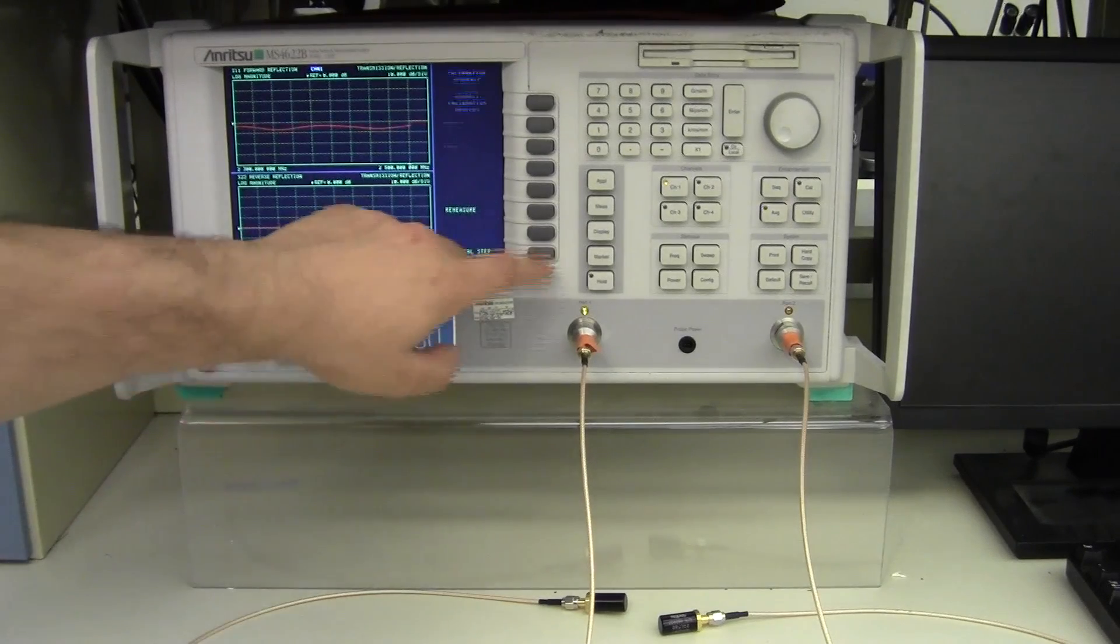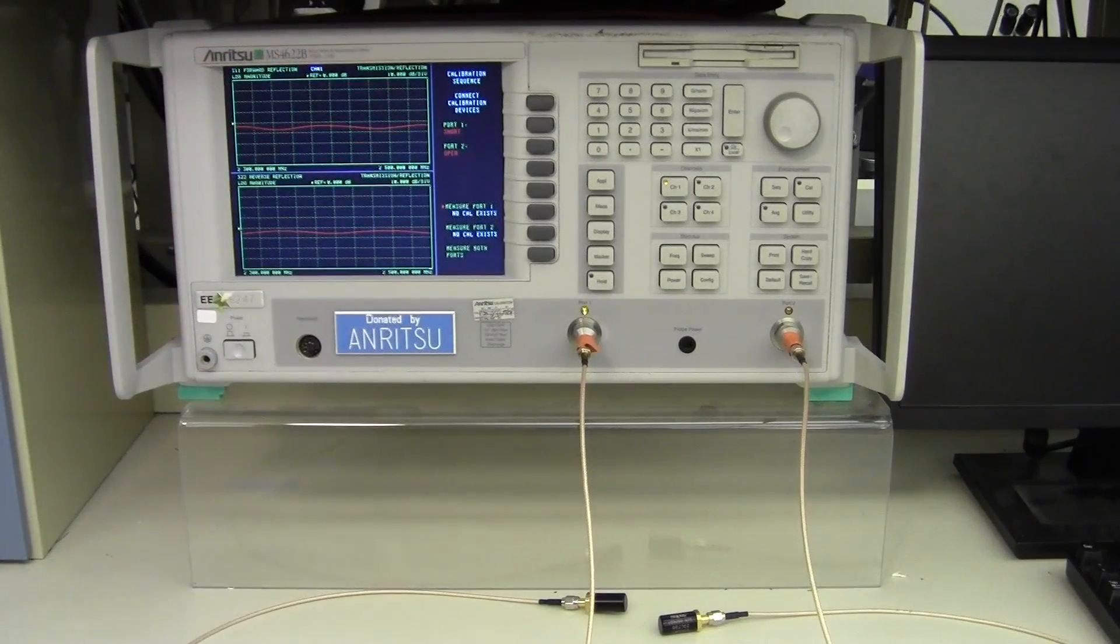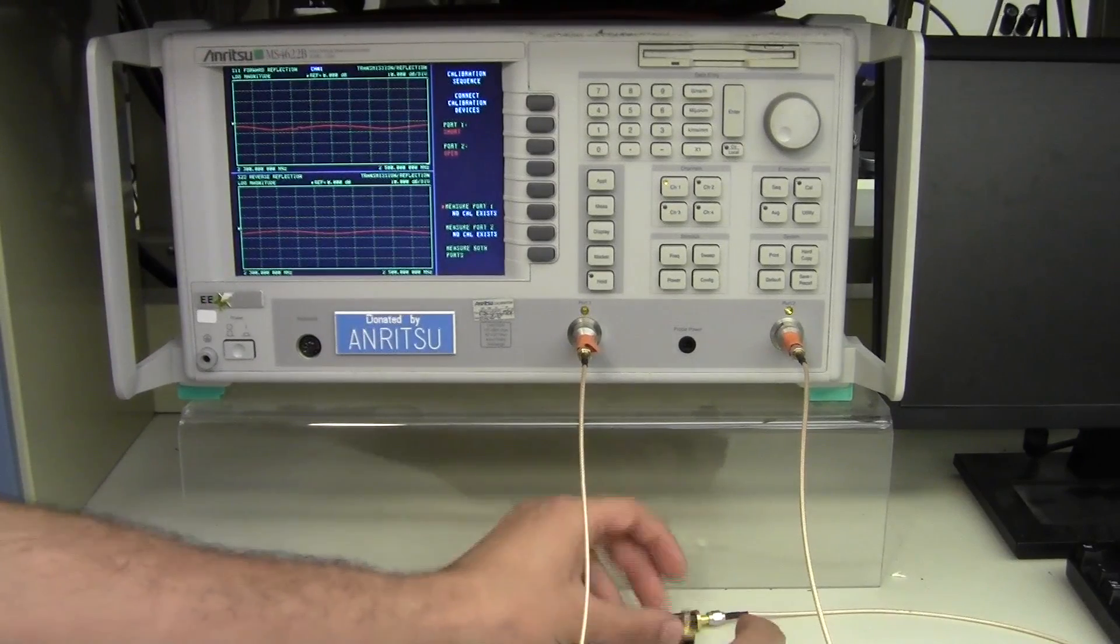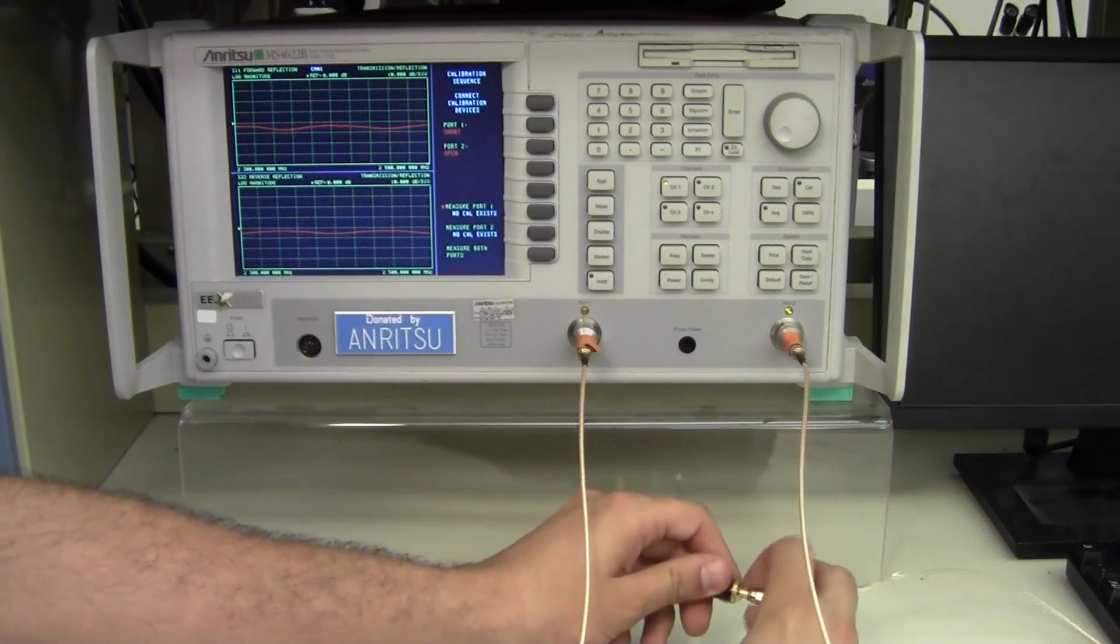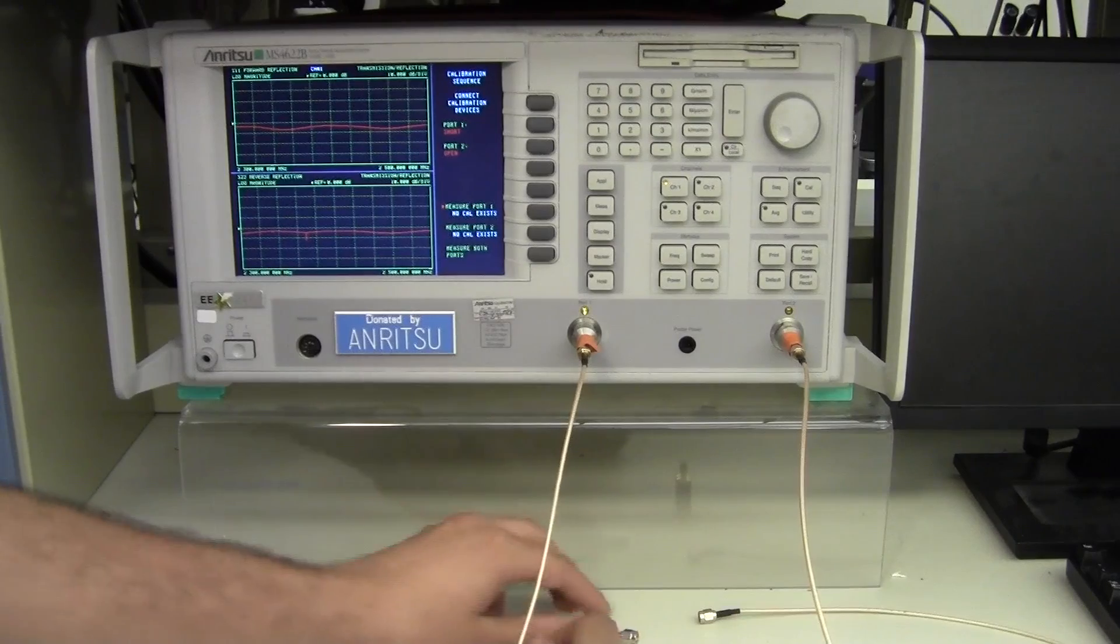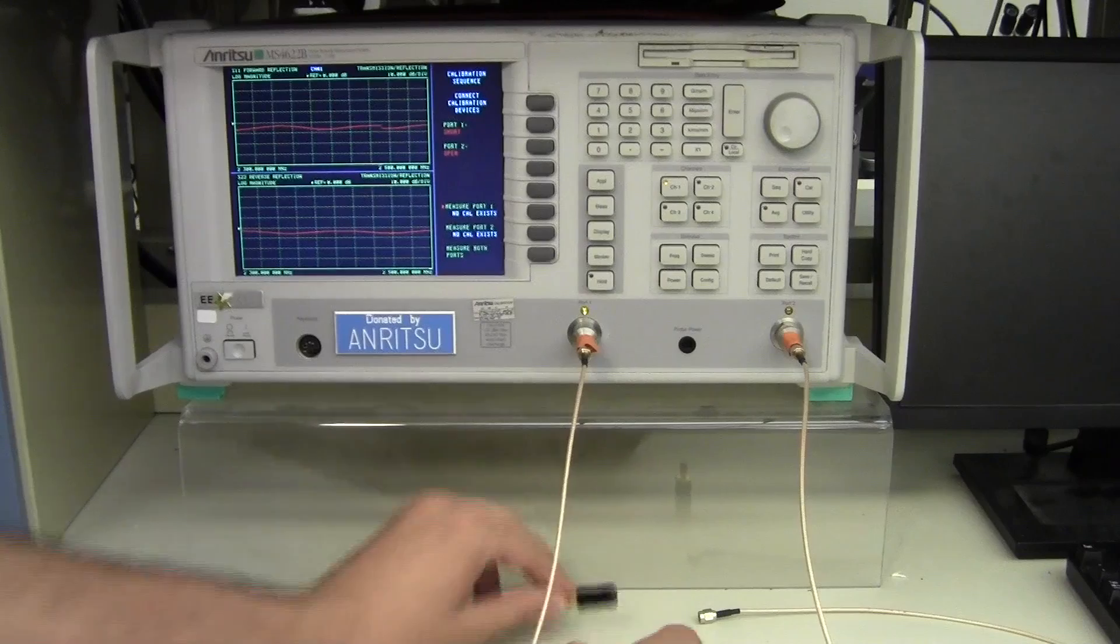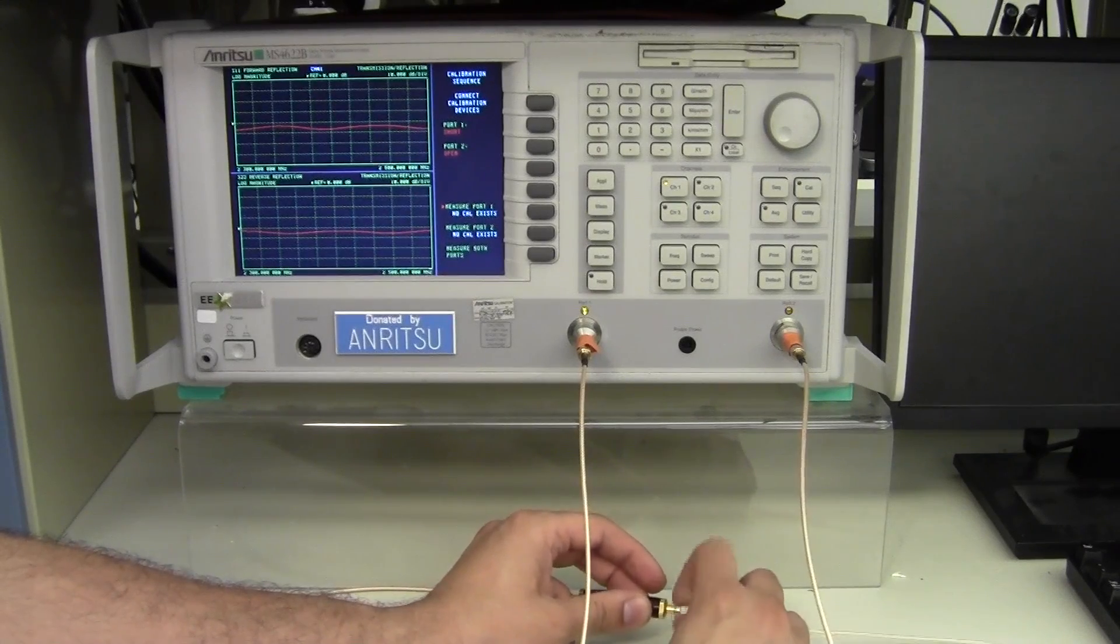Once completed, we go to the next cal step and it asks for the reverse, short and then open. It's asking for them staggered like this since we originally asked for a mixed termination. If we had asked for a match termination at the beginning, it would have asked us for two opens and then two shorts. But our calibration kit comes with one of each, and so we instead opted for the lower cost mixed calibration.